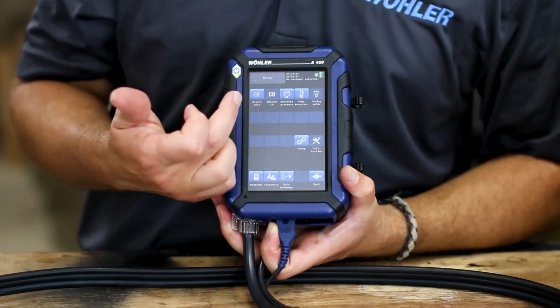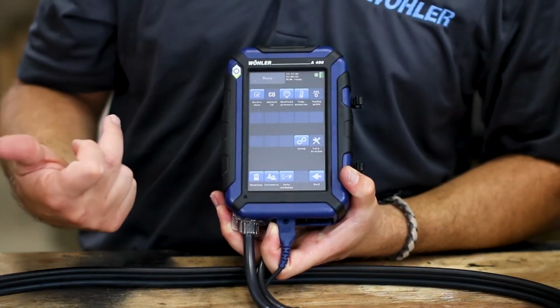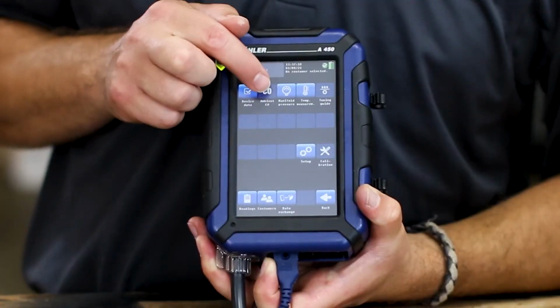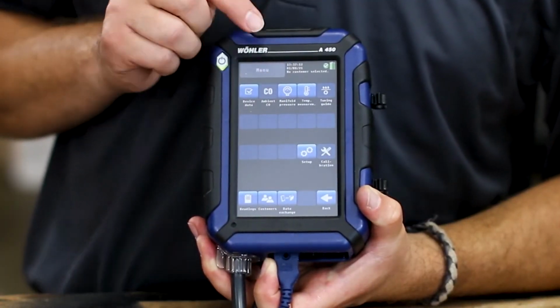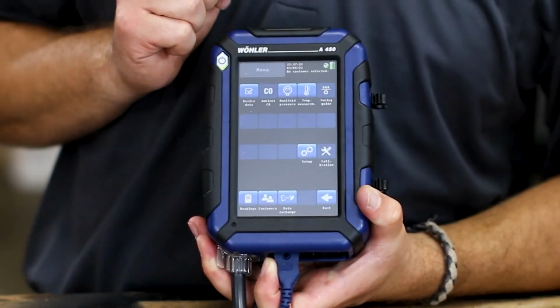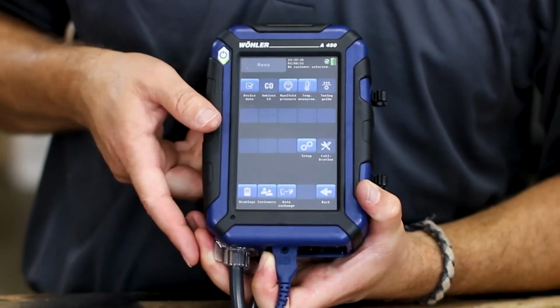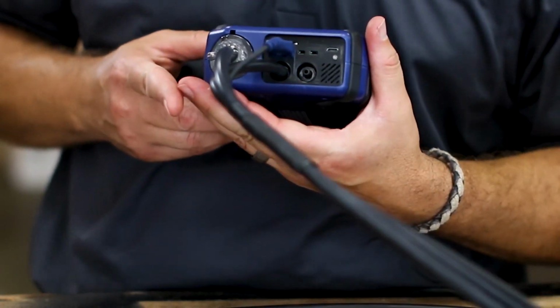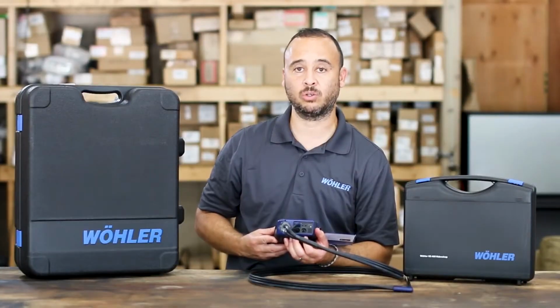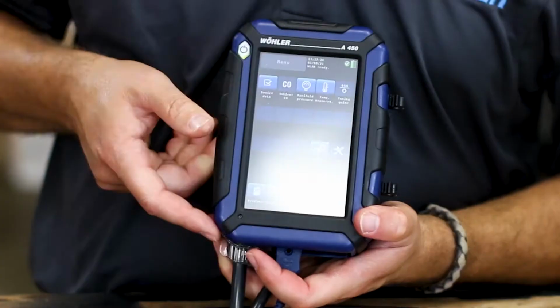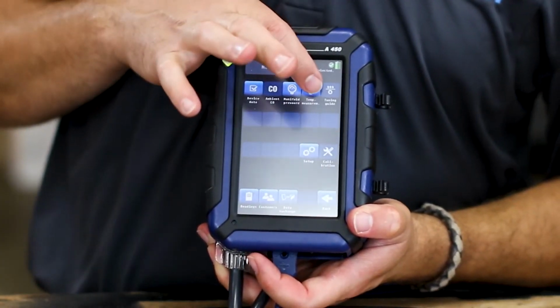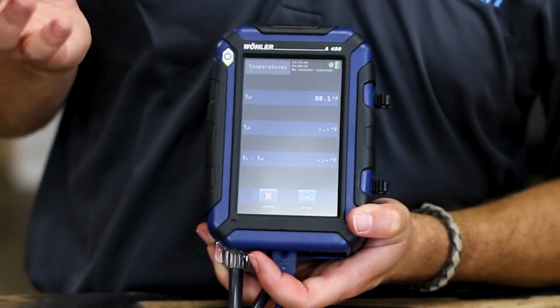Your main header screen is on the very top. You'll have the combustion analysis function, and the manifold pressure, also known as manometer, which is on the bottom side of the unit. Typically you want to use a quarter-inch hose for this function. You also have temperature, which lets you measure ambient temperature and stack temperature with a K-type probe.